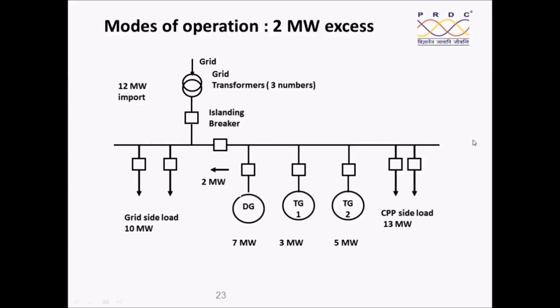In this case, for example, there is a 2 megawatt excess there, and then the islanding breaker trips. There will not be any problem. CPP side load is 13 megawatt. But it may so happen that instead of 2 megawatt, you are pushing about 5 megawatt to the grid side. Assume that the total generation is much higher and 5 megawatt is pushed to the grid. Then, after the islanding, there is an excess generation here. At that time, it may be worthwhile tripping TG1 also, or some other generator also. Therefore, all depends upon your governor control, how your turbine governor is performing. Based upon that, it is possible to ensure that proper islanding happens.